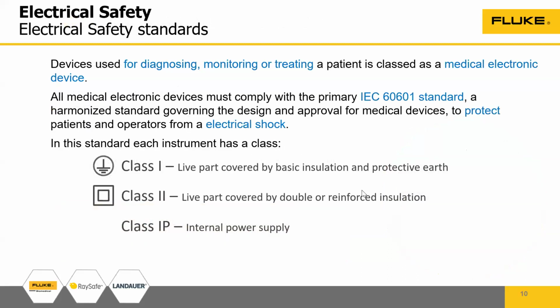The IEC defines devices like class 1, class 2 and class IP, which have an internal power source. Why this classification? Class 1 has live parts covered by basic insulation, and class 2 has double or reinforced insulation. Based on the type of medical device, the testing requirement changes, and so do the recommendations for what kind of electrical safety testing one needs to do.